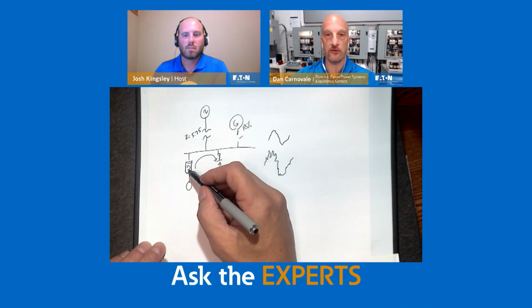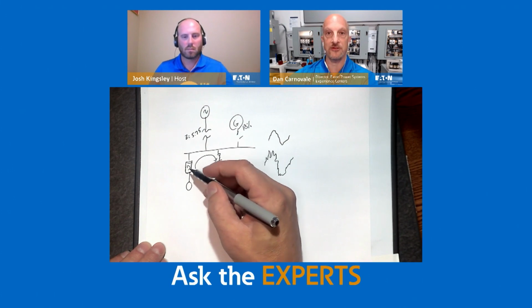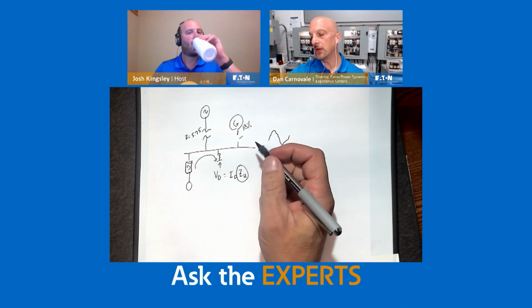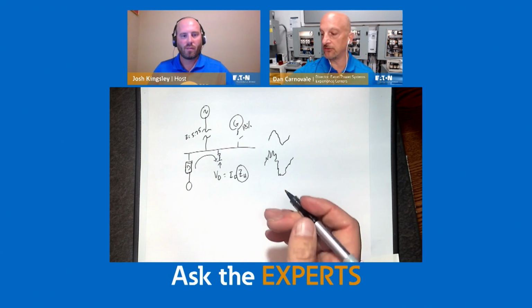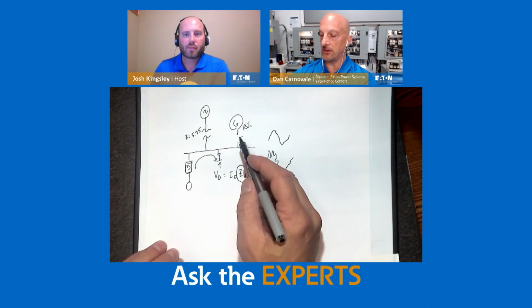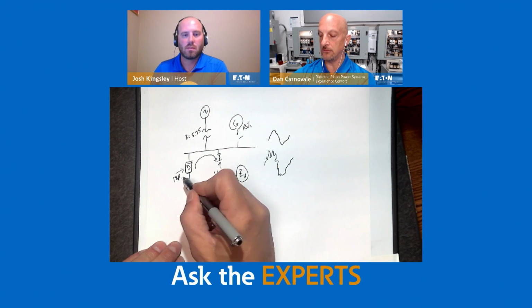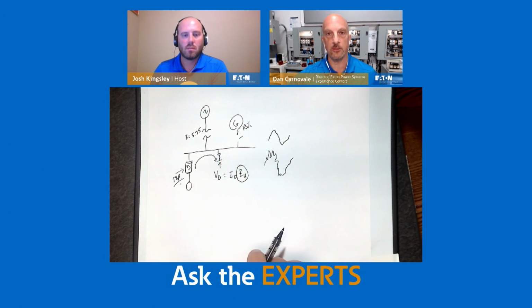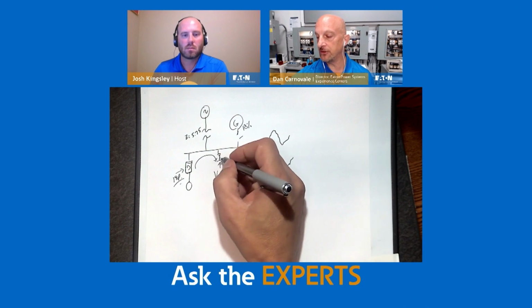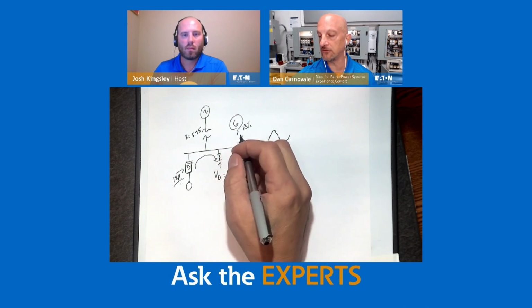And again, this is drawn as one drive, but this could very well be 10 MCCs full of drives. The other thing is, let's say I didn't want to have to deal with this after the fact. If I make this 18 pulse, 90% of the time I don't have to think about it anymore. Sometimes we do passive filters. Sometimes we do active filters.